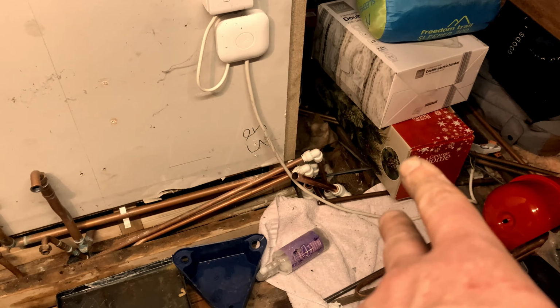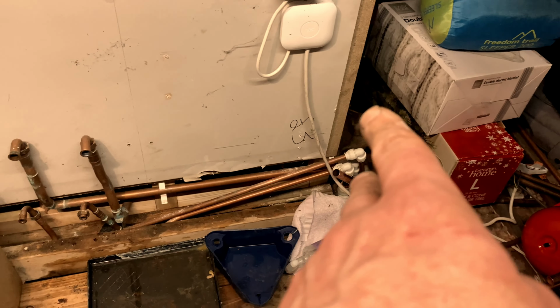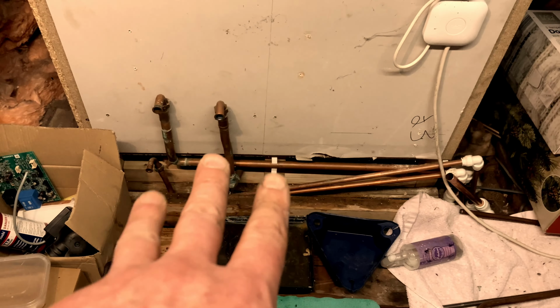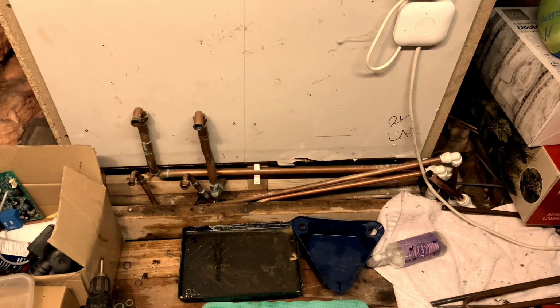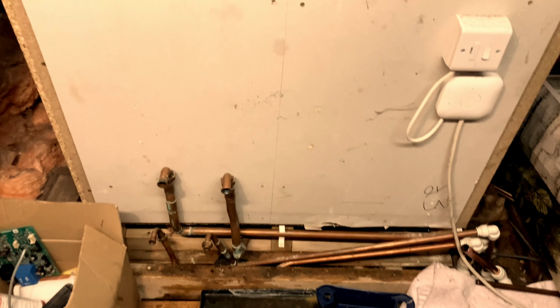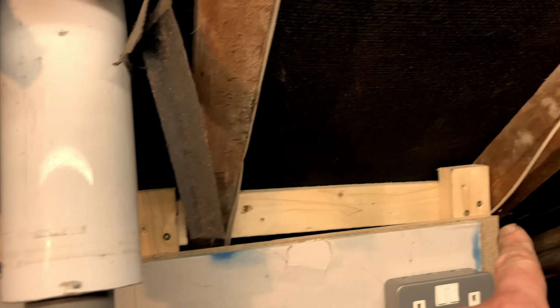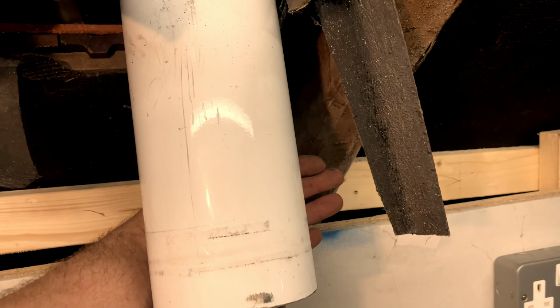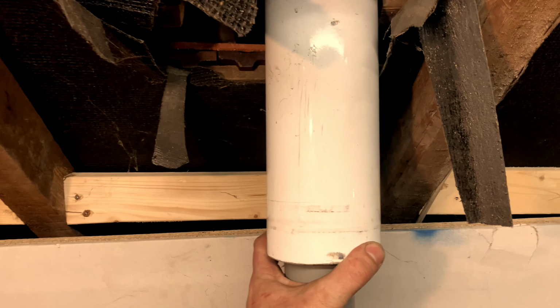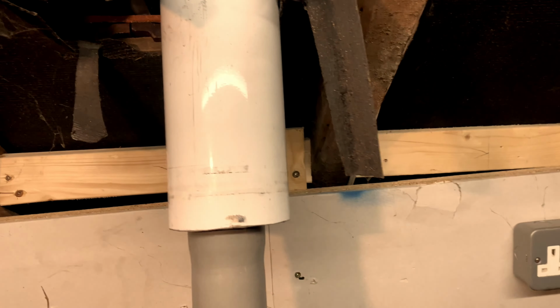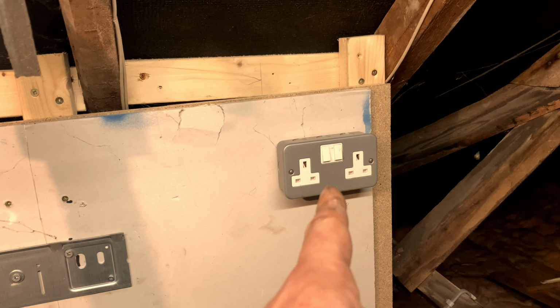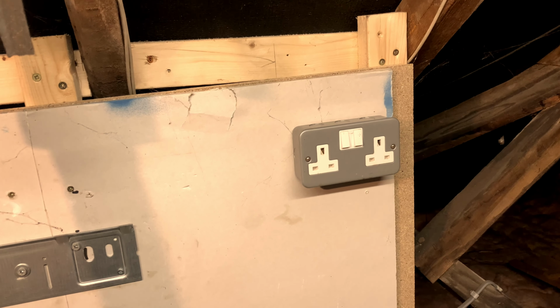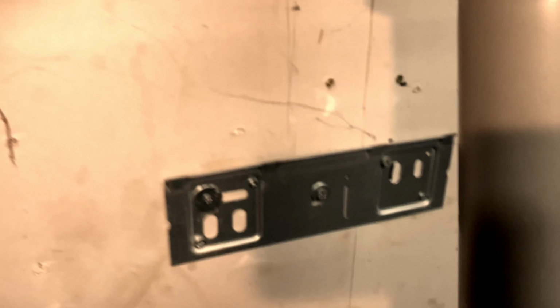So I'm repiping, removing some of that speed fit. 2 rows of clips. There's going to be a magnet filter on it. There wasn't one before. Descaler. Put some extra supports in. The new flue is going to be clipped, bracketed, so it's nice and secure. It's all going to be screwed in. Socket there to meet regulations for the flue analyzer and lights. I've got the bracket in. It goes through the other side with extra supports.